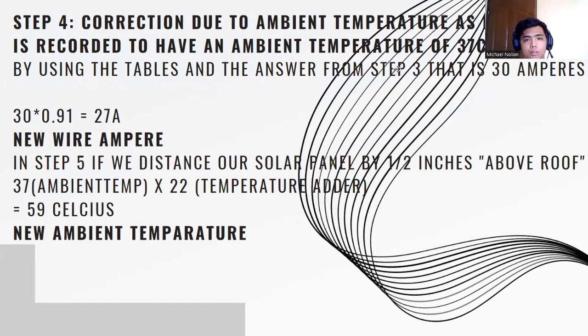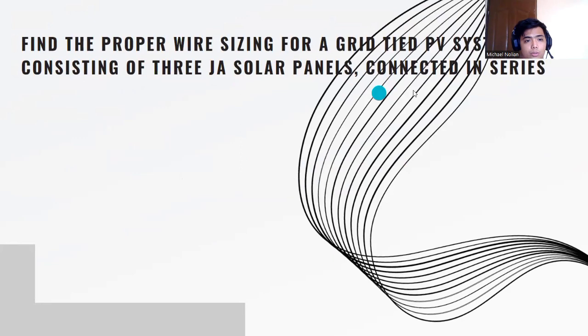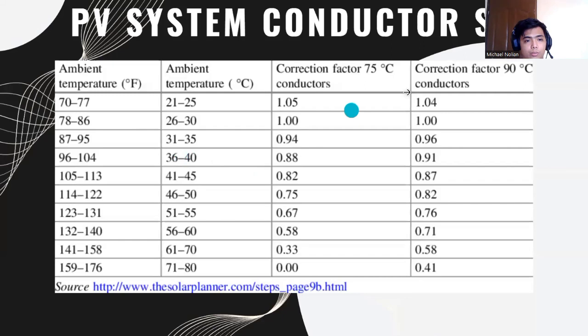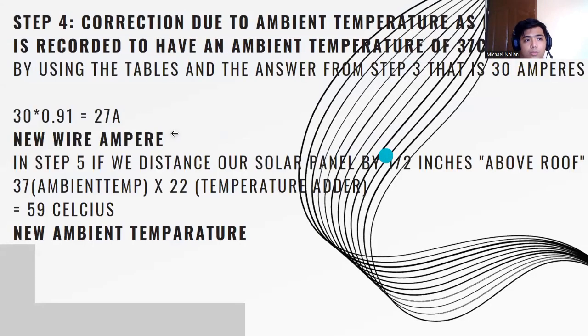Using the table and the answer from step 3, that is 30 amperes. Checking again, 30, see, 37. This is the ambient temperature. The correction factor for a 90 degrees Celsius conductor is 0.91. We multiply it by 30 amperes, and we get 27 amperes. So this is our new wire ampere.